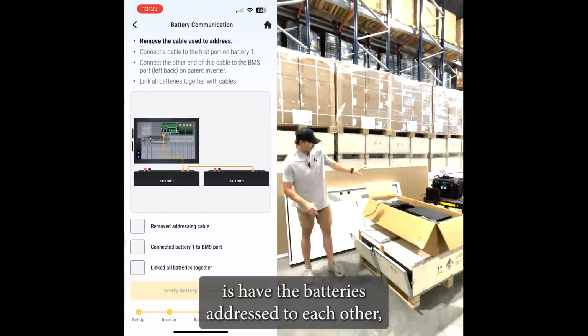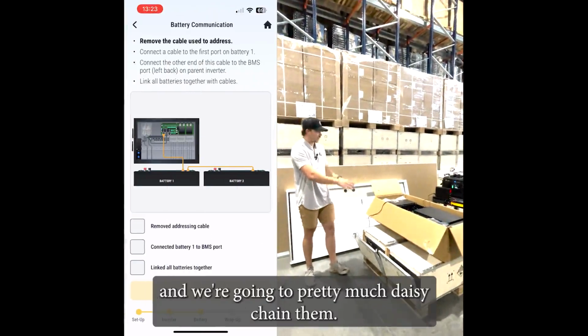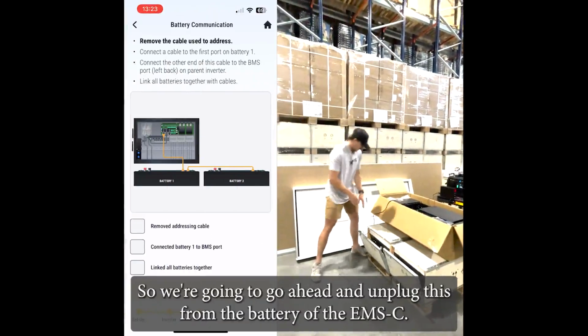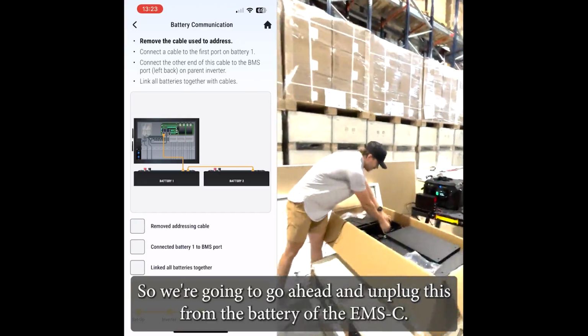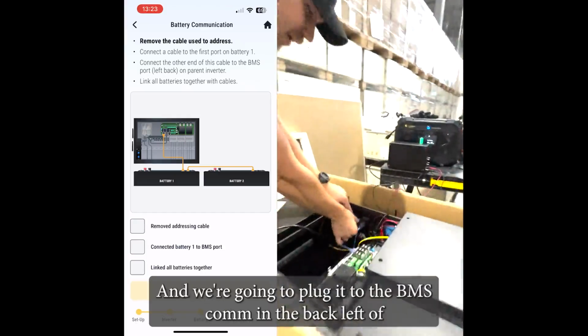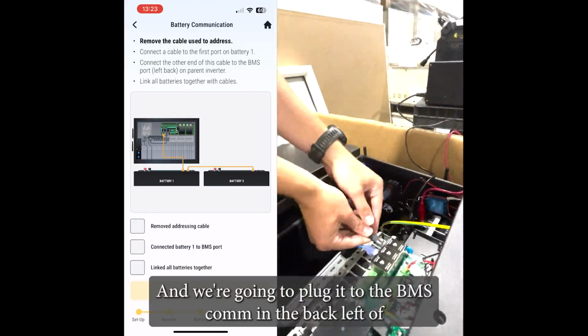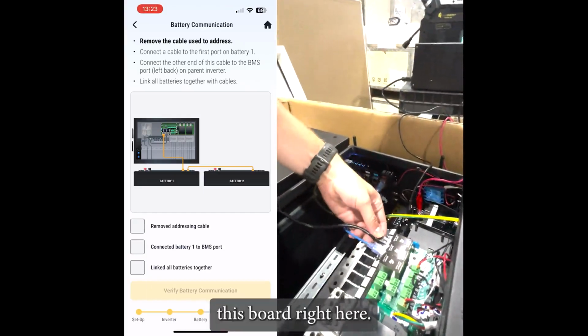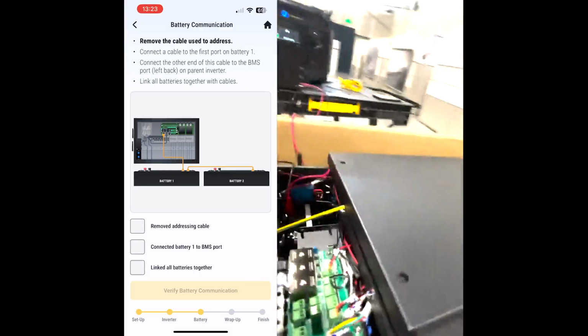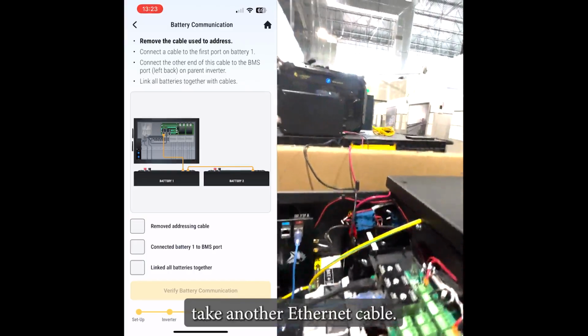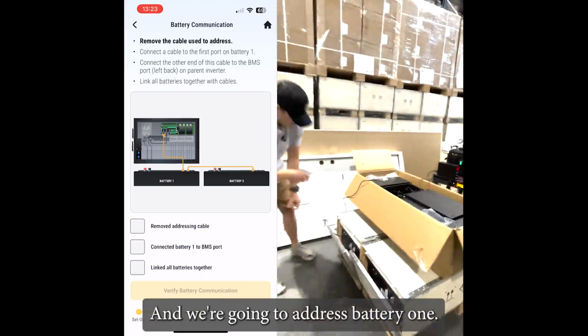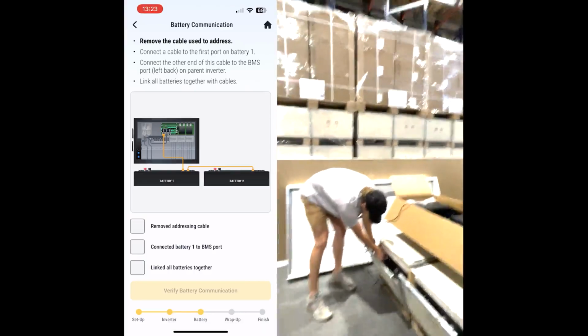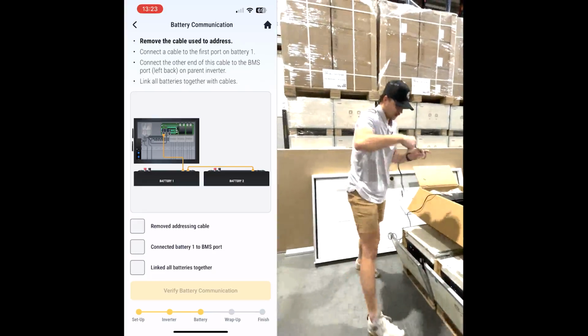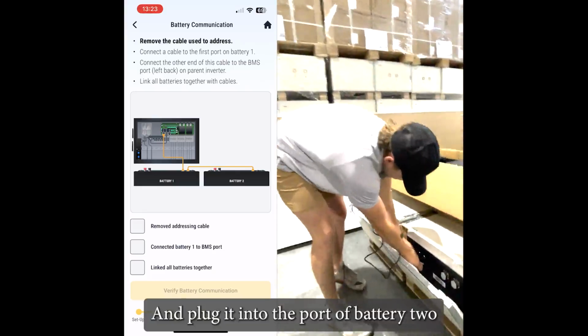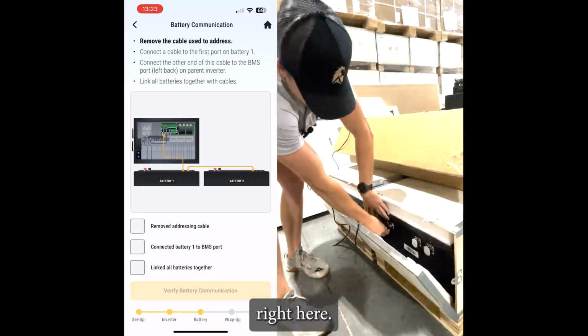Now we're going to have the batteries addressed to each other, and pretty much daisy chain them. We unplug this from the battery port of the EMSC and plug it into the BMS comm in the back left of this board. Then we take another Ethernet cable, address battery 1, and plug it into the port of battery 2.